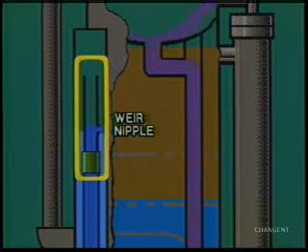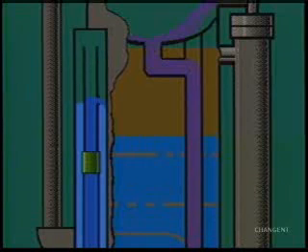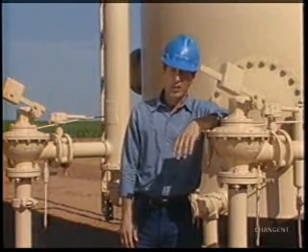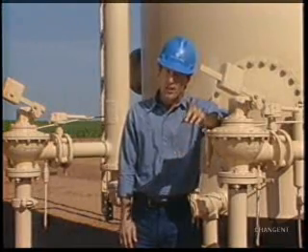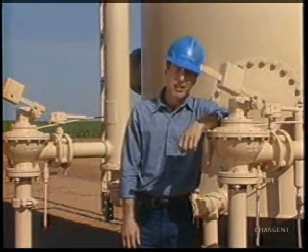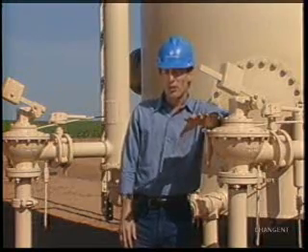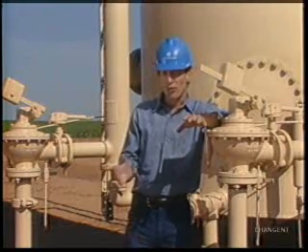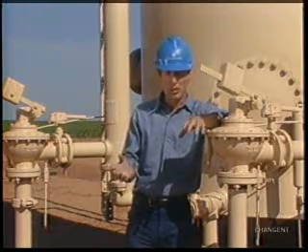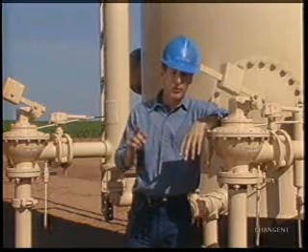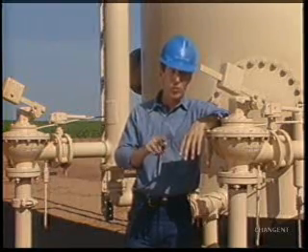Some treaters use an adjustable siphon or weir nipple to change the water level. On these, a one-inch adjustment of the nipple will move the interface height about four or five inches. Heater treaters designed for cold climates often have the siphon line built inside. On these, the siphon box is either outside for accessibility to the siphon nipple, or the nipple is adjusted from the top of the treater through a control mechanism.